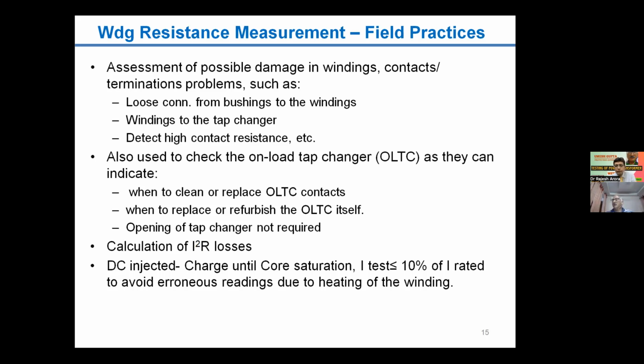And many times while charging the transformer, those were the days when even the differential relay plugs were set before switching on the transformer, and sometimes even the trip command was isolated. Nowadays all these things are taken care of through numerical relays, where you adopt different settings when switching and you may avoid tripping during charging. So, again coming to the same topic, winding resistance measurement.